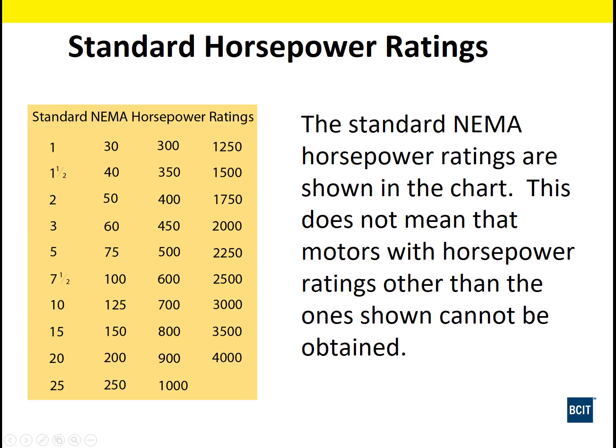Now we have standard horsepower ratings for all motors. NEMA established this standard a while ago. It has 1, 1.5, then it goes up 2, 3, 5, 7.5, 10, 15, 20, 25, 30, 40, 50, 60, all the way up. The higher the horsepower, the larger the increments between sizes. Now you can get higher than 4,000. You can get up to 20,000 horsepower for some of these motors.